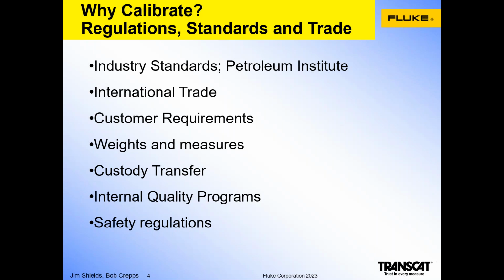They're required for international trade. Sometimes the customer of the products that you manufacture in your facility require that calibration records be maintained and available for audit. And then, of course, weights and measures, which are often used in the batching of processes. A good example would be in the pharmaceutical industry, where any items that are being manufactured, the weights of ingredients that go into a process batch need to be carefully weighed, and of course measurements of that process batch, the temperatures and pressures that the batch is processed at, all have to be documented and recorded and measured by traceable measurement device instruments in the process.